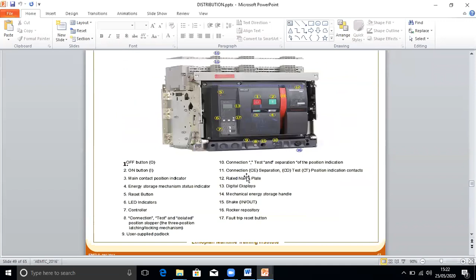So this is one air circuit breaker you can see here. On this air circuit breaker, you will find a manual stop button, a manual on button, and this is the handle. This handle you can also use for charging the springs. The charging spring is a motorized spring, by which this breaker gets closed. Suppose you lose the power completely, there's a blackout, and you try to push this, it will not operate. In such conditions, you need to charge it up using the handle. This handle, number 14, is a charging handle. You charge it and you find the indication of whether it is charged or not.